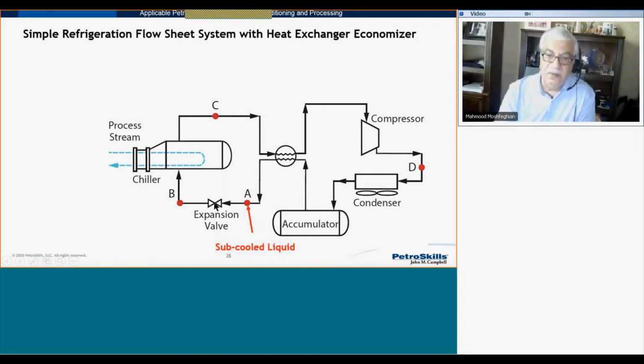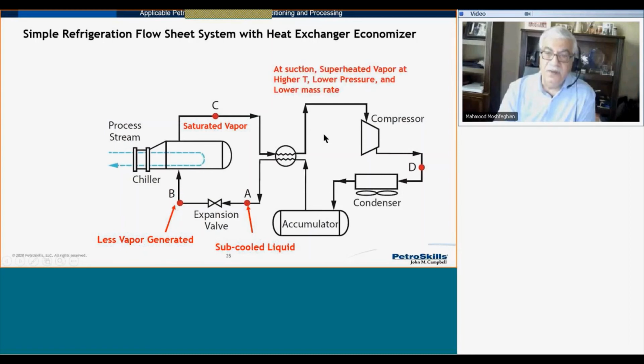Then I go to the JT valve. So I have this fraction of vapor, which is good. My mass flow rate is going to be lower now. But when I come out, say saturated vapor, this saturated vapor is going to get heated up, becomes superheated, as well as pressure goes down. So what I have through my compressor is superheated vapor at higher temperature, lower pressure, and lower mass flow rate.